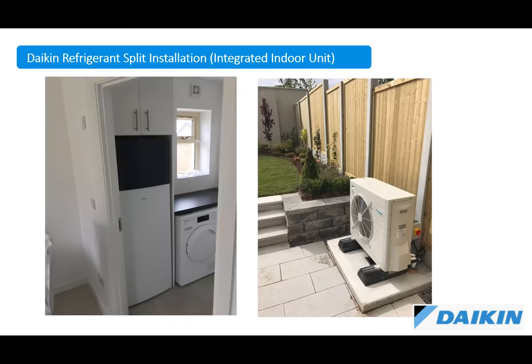So just images, I'm looking at the time ticking down here, so I'm starting to speed up. Some images of how the outdoor unit should be installed, and you can see there it sits on the rubber feet. They're anti-vibration feet so that the vibrations are not going to damage anything internally in the heat pump. You've got a drain underneath the heat pump so that the water can drain away from the heat pump when it starts to run off. And then you can see the really nice integrated indoor unit. It just fits into a cupboard, and it's taken up the same footprint as the tumble dryer next door to it.